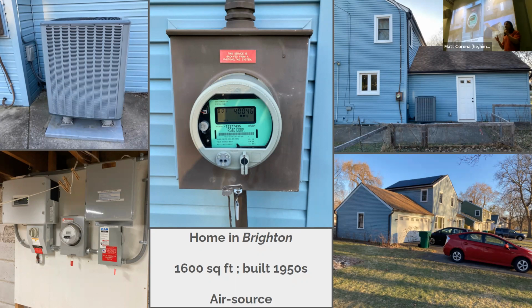If you want cold climate heat pumps, you can basically reuse the system you already have and just add the outdoor unit, saving around 40 to 50% of the install cost. But if you have to replace both heating and cooling at the same time, I'd recommend just going straight cold climate heat pump. If you have a ducted system, most will come with electric backup built in, because if it got to -20, for example, the system would be working as hard as it could and would need that backup to make up the difference to stay at temperature. But if a system is designed and sized properly, it will almost never have to do that.